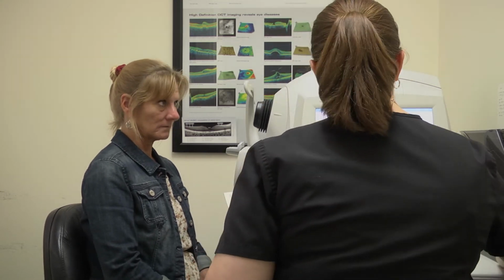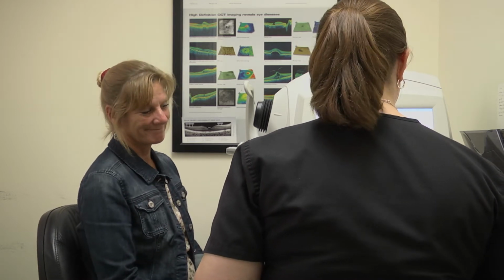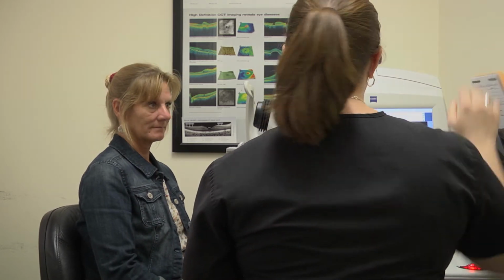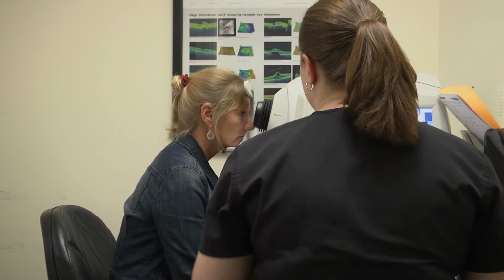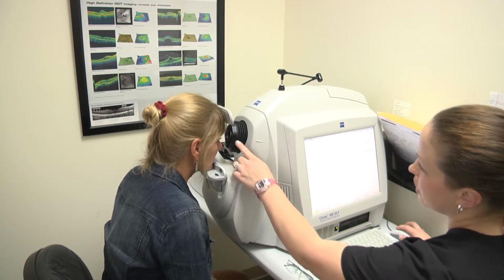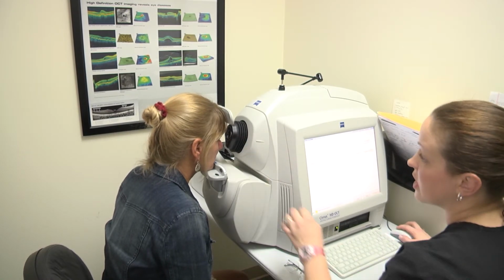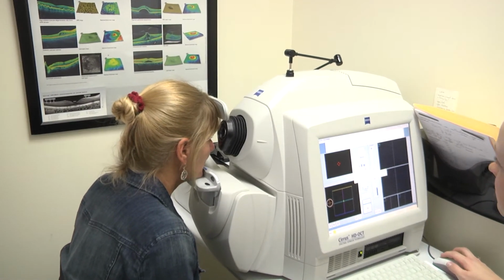You'll walk the patient into the room, have them take a seat in the chair, and wait for just a minute so you can put their information in. Once the information is in the machine, you'll instruct your patient to come forward to the chin rest, forehead nice and tight against the headrest. Now they're going to focus on a green star. Have them look directly in the center of that green star.